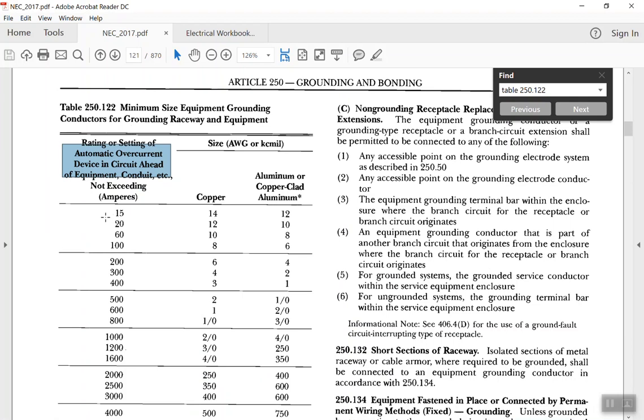45. And you say, well, 45 ain't there, so I'm stuck. No. 45 falls right in here, doesn't it? So when we size up to 60 amperes for the fuse, in this case dual element fuse, and slide over to a number 10. Slide over to a number 10. So let's go ahead and put that in our notes, and we just knock this thing out.